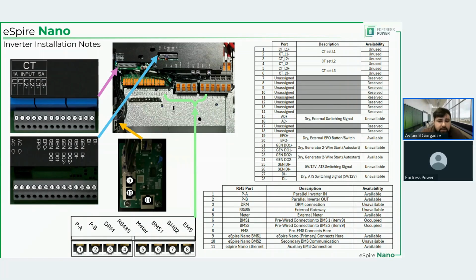And eSpire Nano Ethernet. This is not necessarily for connecting Nano to the inverter. This is for you to be able to connect to Nano while it is in communication with the inverter. Let's say with your laptop, you're going to connect your Ethernet cable, type in the appropriate IP address, and you'll be able to communicate to the battery while it is already communicating to the inverter. So it's an Ethernet switch of sorts, that 9, 10, 11, that board on which it sits, especially on port number 11. It reminds me of an Ethernet switch very much.